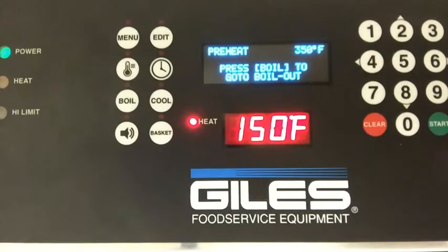So let's go back. We're going to put this back in the cook. The yellow light comes on, and we're going to allow this unit to go ahead and start heating up. And of course we're looking for 350 degrees as our set point. It's going to jump a little bit quicker than it normally would, only because I'm trying to do this with a simulator. So you'll see the numbers will start to scroll up pretty quickly, and we're going to ease on up towards that.